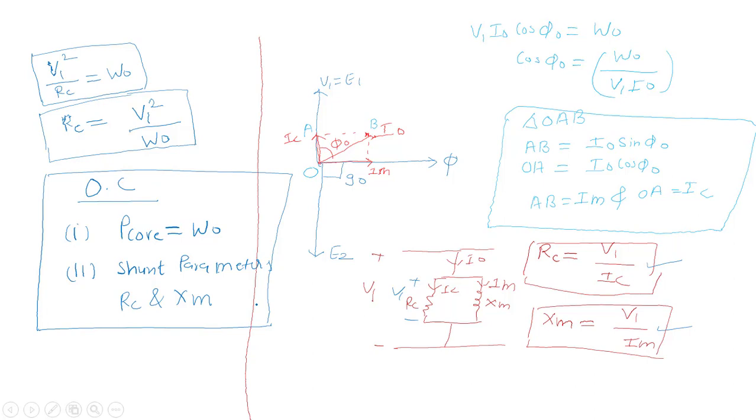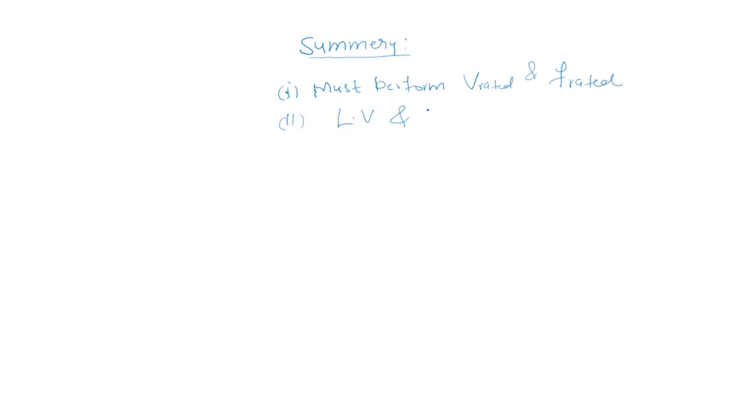Okay, so let us quickly summarize this open circuit test. If we look at the summary, the open circuit test must be performed at V rated and F rated. Second thing that we can summarize, it must be performed on the low voltage side, and the high voltage side must be open circuited.